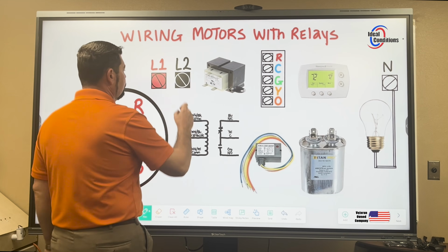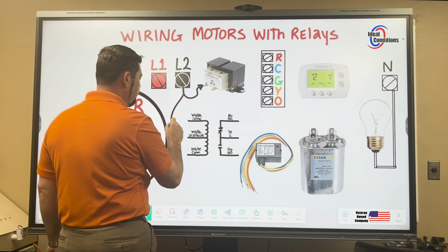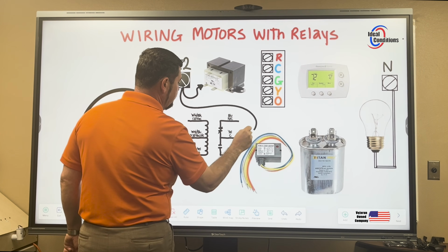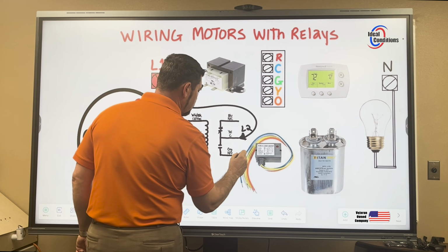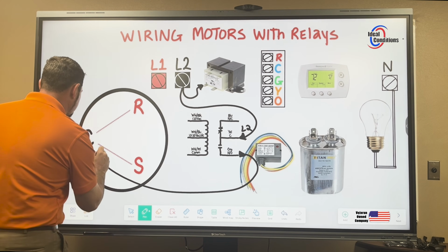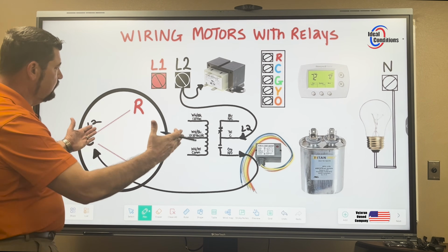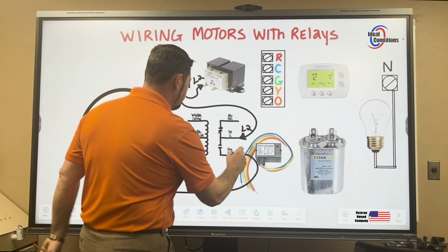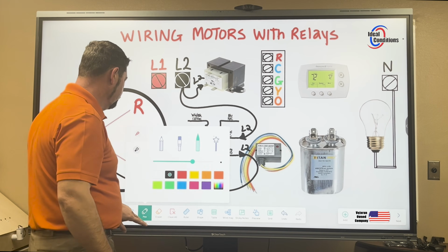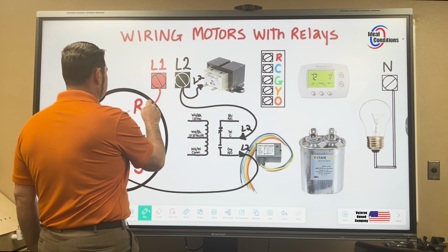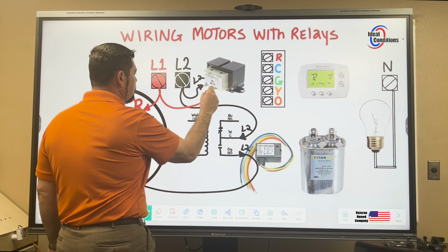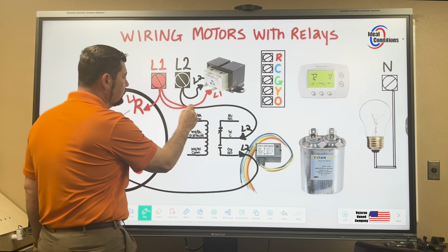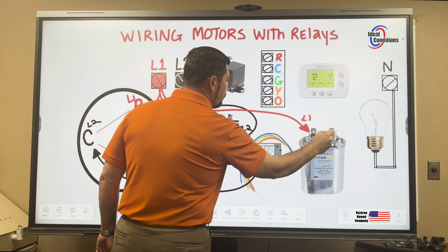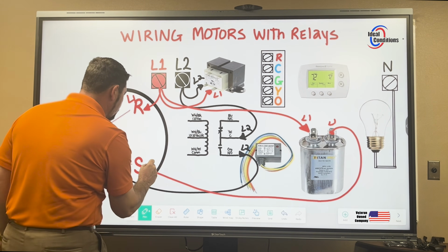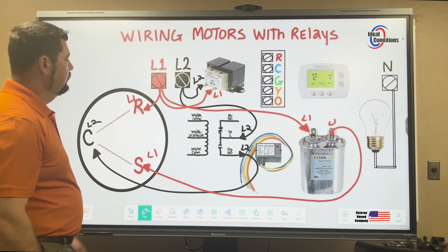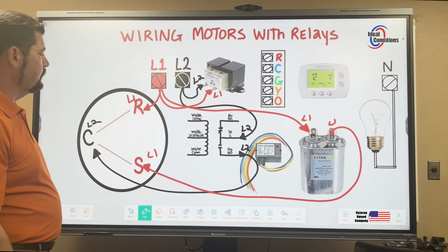simply, we're going to go ahead and, like I said earlier, we're going to wire everything that needs to have L2 output. Inspect it. L2, L2, L2, L2. We're done with L2. We're going to come over here. We're going to wire up L1. L1. We're going to come over here. Give our capacitor L1, come out of here, over to our start winding. That's obviously L1 also. Now we have our L1 and L2 100% completely done.